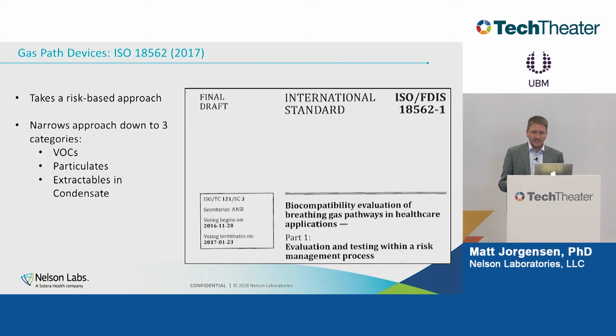If you have a respiratory contact device, this standard applies to you, targeting the biocompatibility of these devices. This was really too long in the making. I wish it could have come sooner, because respiratory contact devices, like an oxygen concentrator, aren't amenable to the classic methods of evaluating biocompatibility. A lot of these oxygen concentrators have an artificial zeolite material inside that explodes on contact with water. So how would you evaluate this by extracting it with some cells or putting it on an animal? It just doesn't make any sense.